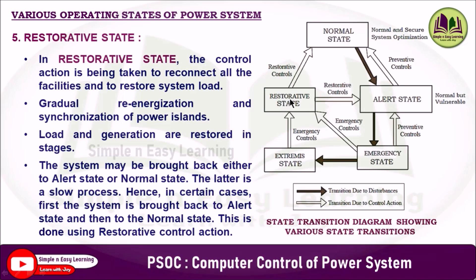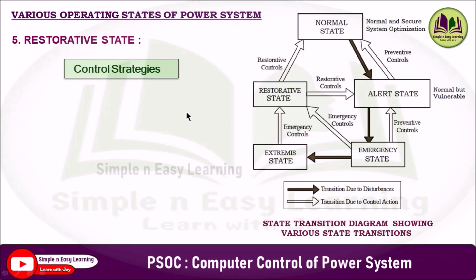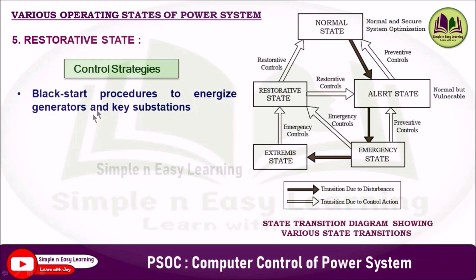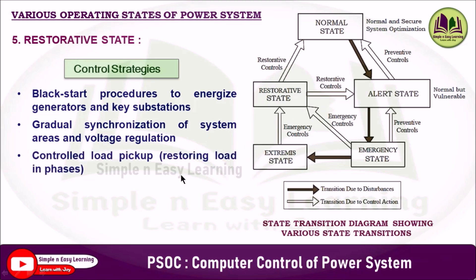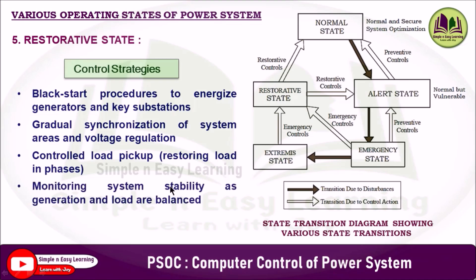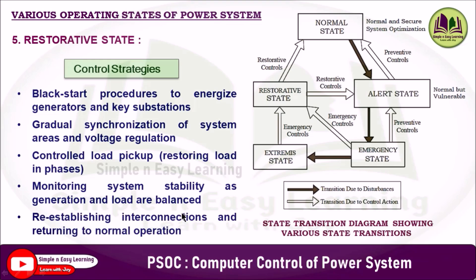Control strategies in the restorative state include black start procedures to energize generators and key substations, gradual synchronization of system areas, voltage regulation, controlled load pickup (restoring load in phases), monitoring system stability as generation and load are balanced, re-establishing interconnections, and returning to normal operation.